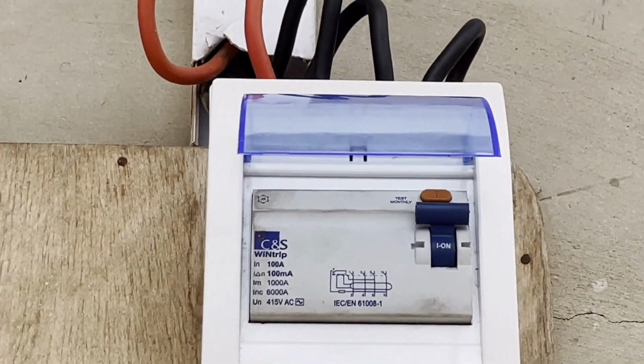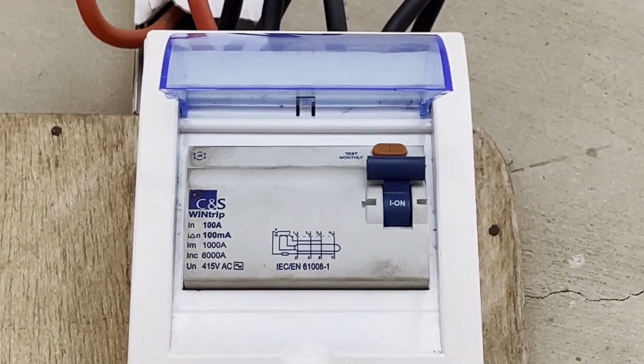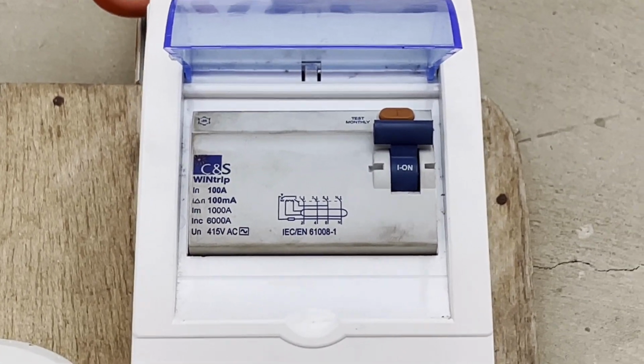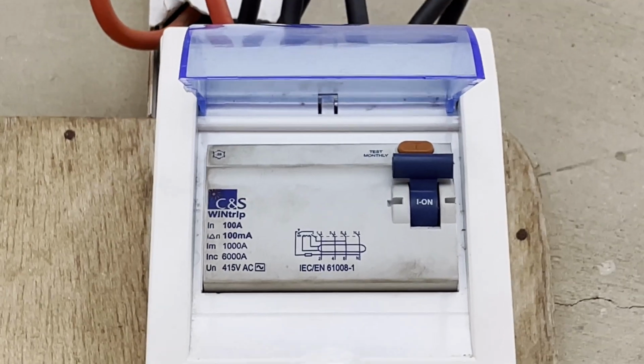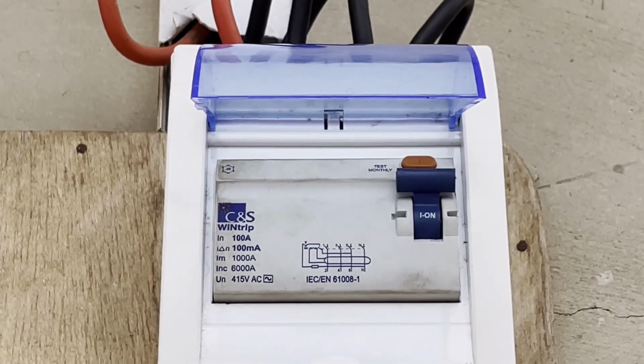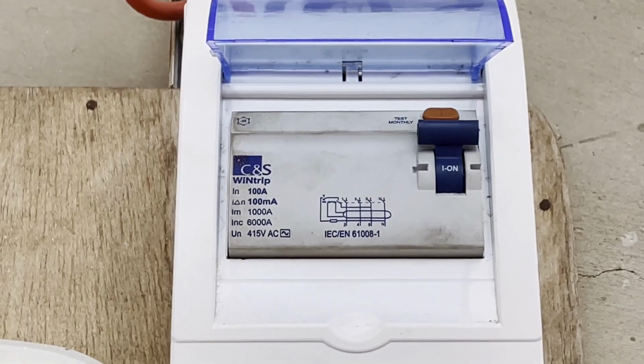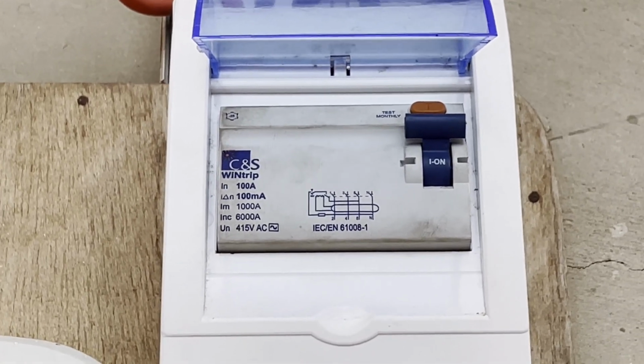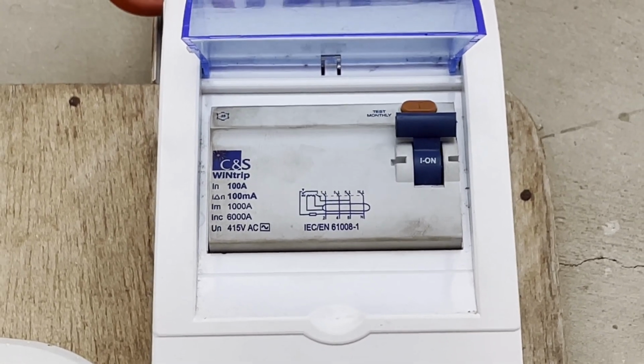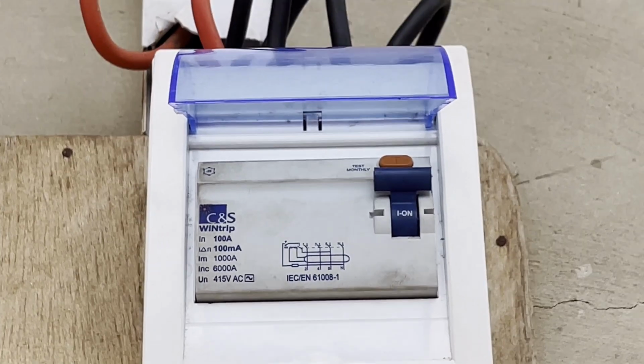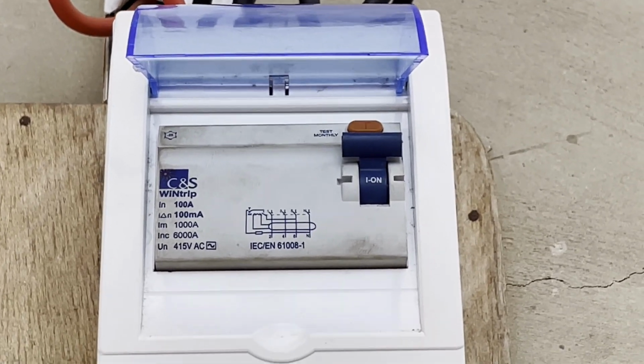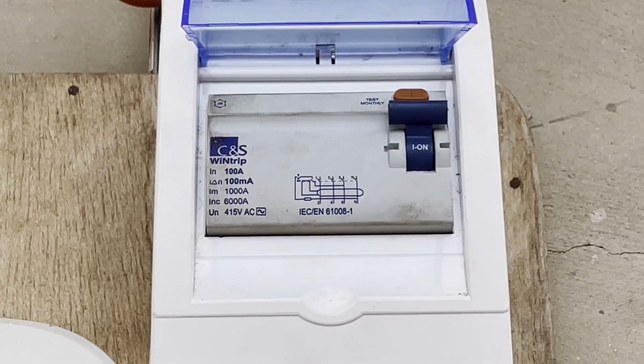Now you can see the rating is 100 amp for the size of my house, 100 amp. The sensitivity is 100 milliamps. And it's a three phase and neutral device, because I've got 3 phases coming into my home, hence the 415 volts. So that's what you should typically see if you're going to get an RCCB yourself.